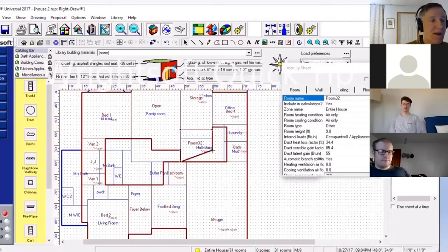This calculates infiltration and conductive heat losses through the walls. It deals with radiant heat transfer from the roof, especially. It even considers window issues, even the reflection off the ground. It takes into the geometry of overhangs. Where the sun is shading windows and walls, it looks at that. And it's really straightforward. It's so easy, it's almost a little scary. You can put in your construction materials, start drawing this, and boom, you get a load calculation.